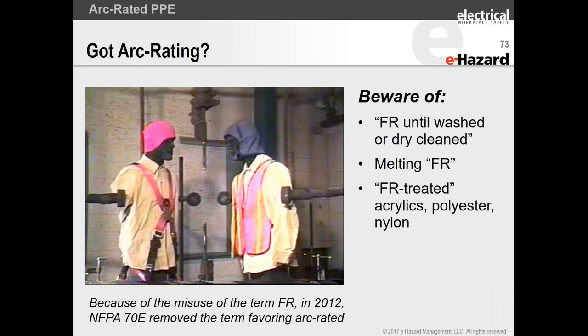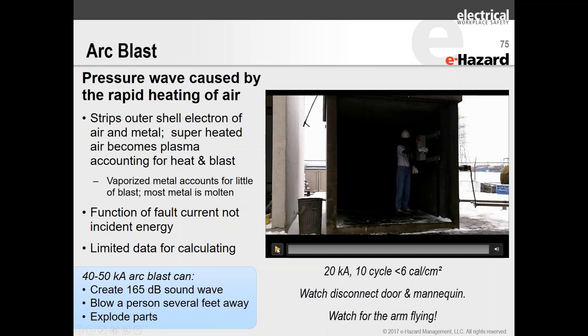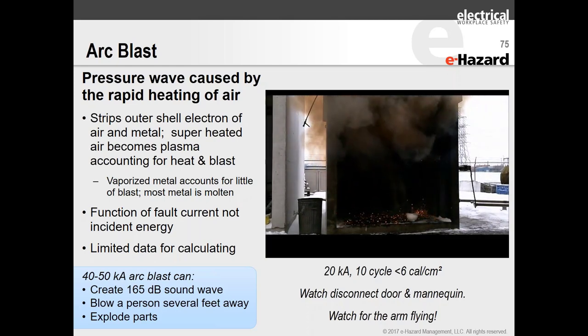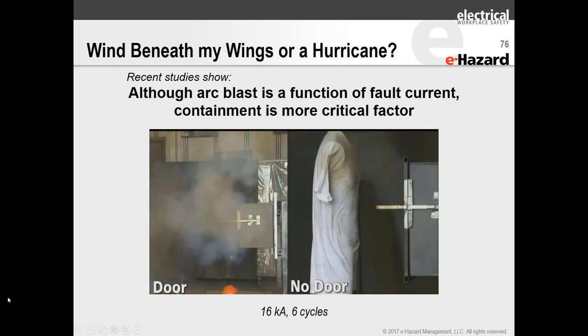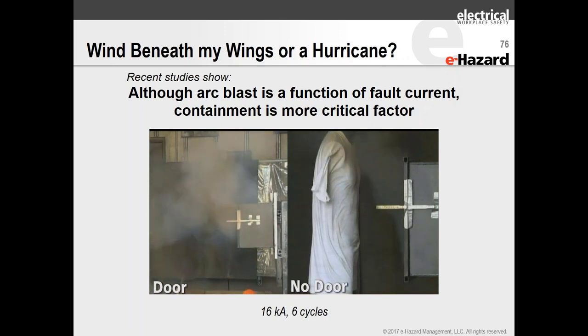FR and AR: it's important to make sure your clothing is arc-rated. FR was removed in 70E 2012 because the term was misused so widely. You can actually melt FR if there is an incident. Pressure waves are also important — in a demonstration with a mannequin at 20 kA, 10 cycles, less than 6 calories, watch the disconnect door and the mannequin arm being moved by the blast. Containment is a more critical factor than arc blast as a function of fault current — the risks are very different in a contained fault versus an open fault.